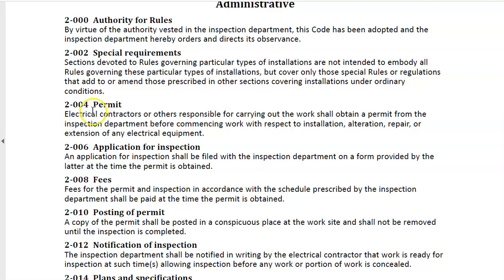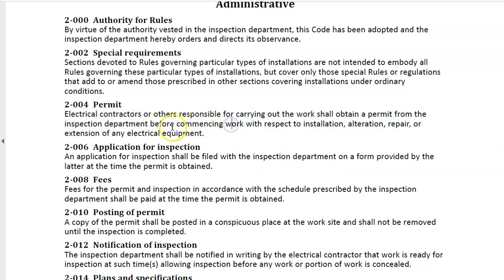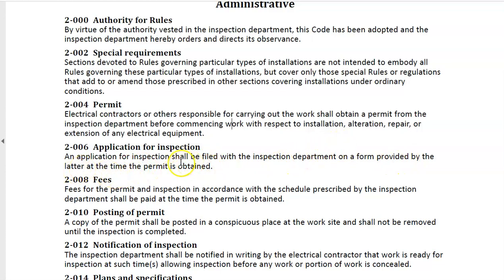Electrical contractors or others responsible for carrying out the work shall obtain a permit from the inspection department before commencing work. That means you get the permit before you start the job with respect to any installation, alteration, repair, or extension of any electrical equipment. You also have to request an inspection as part of that permit, filed on a form provided by the inspection department at the time the permit is obtained. A copy of the permit shall be posted in a conspicuous place at the work site and shall not be removed until the inspection is completed.